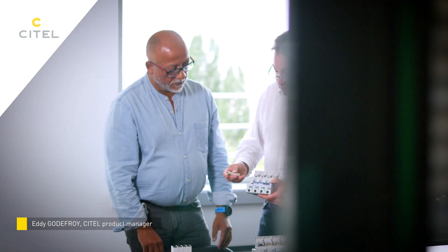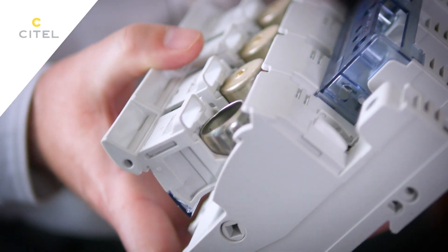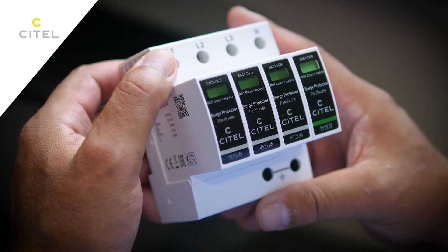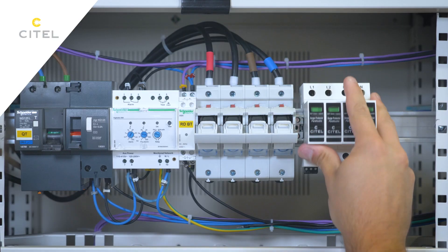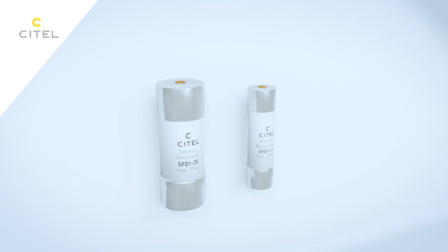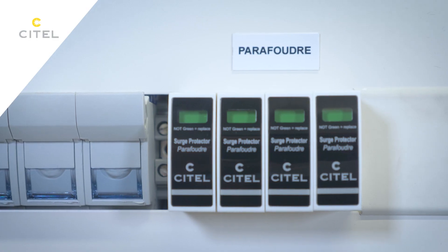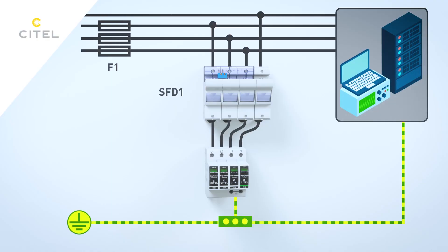To comply with the standards, low-voltage surge protectors must be protected against short-circuit currents. CITEL has developed a new range of surge protectors using SFD to be associated with Type 1 surge protectors. Fused disconnectors must be installed in the parallel branch of the surge protector.